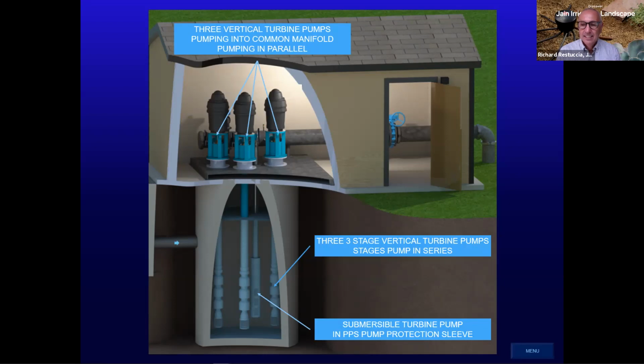Generally, if you have a 5,000 gallon a minute system and you might sometimes only pump 500 gallons a minute, you don't want to use a single 5,000 gallon a minute pump in the application, because at the low end they operate very inefficiently, and there are various other issues that can come up. So you want to phase pumps in as demand increases so the system can run more efficiently. That's the rationale behind it, and in many cases you have a little bit of redundancy as well. Okay, good. Thank you. You bet.